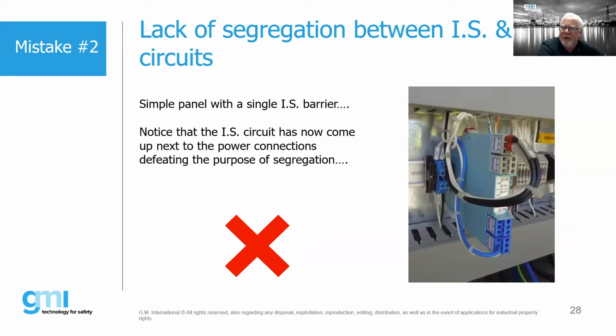This is a simple example. This is a panel with a single barrier. If we look down at the bottom, we see our IS coming out, and we see some power coming in. But then all of a sudden, we've taken this IS circuit and looped it up into some sort of duct, and we've run that right next to probably some power conductors. So we need to have a separation between power and IS, and there are different ways of achieving that, which we'll talk about.